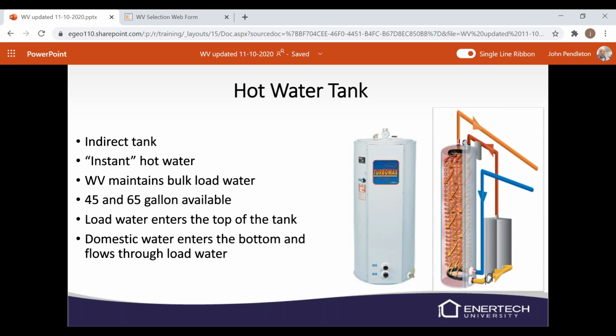The WV hot water coming into the tank enters the top and comes out the bottom and returns back to the WV unit. So we've got bulk water in the outer jacket and domestic hot water running through a coil and runs through the load water. And we do reverse return on the water flow. So the coldest domestic water gets the coldest water from the WV unit, and vice versa. The hotter domestic hot water gets the hotter of the WV unit. Better heat transfer that way.